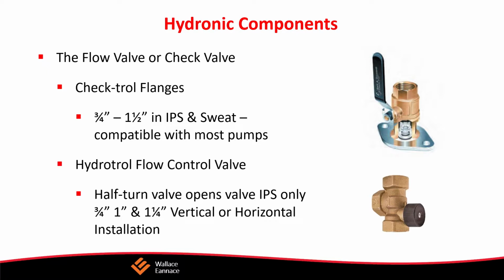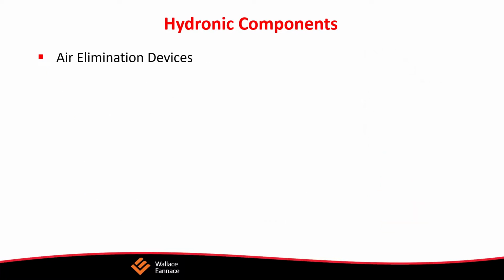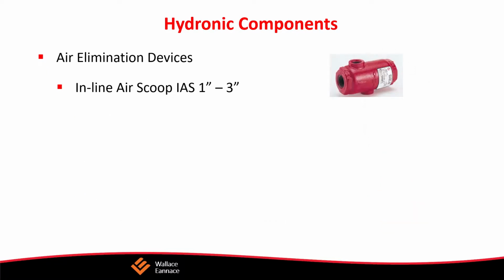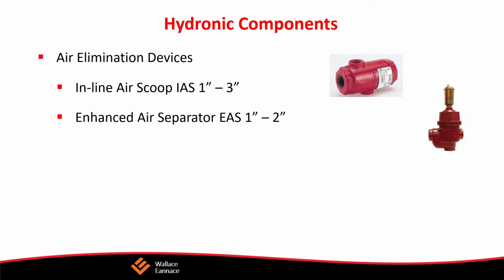So after the system pressure is set and we fill the system, by rights, you really should shut off the valve before the reducing valve. Now, a lot of people say, well, what happens to the boiler from dry firing if there's a leak? Well, the PRV is not designed to protect the boiler. It's only to assist installing and setting the correct system pressure. The pressure is set. You have a low water cutoff on the boiler, which is by code on all boilers. That low water cutoff, that's what actually protects the boiler. If you have that open valve, what you're going to end up doing is you're going to end up having a flood.